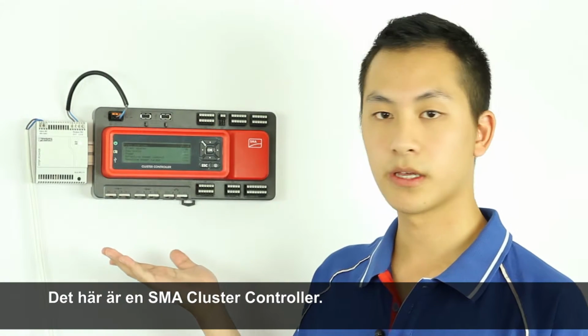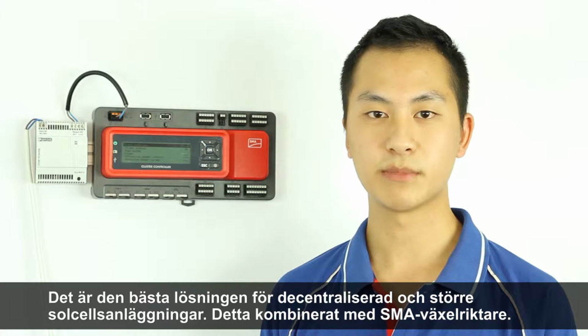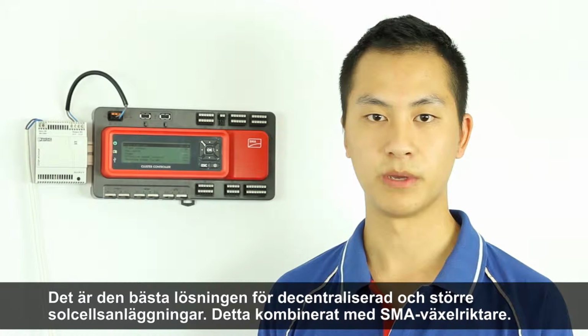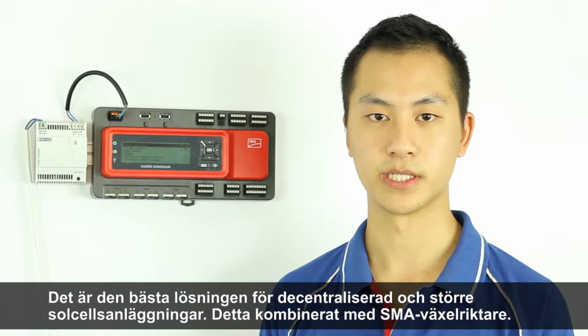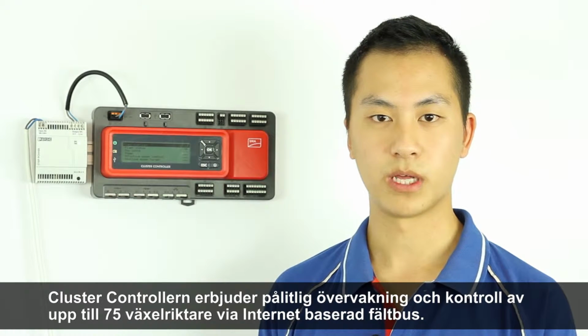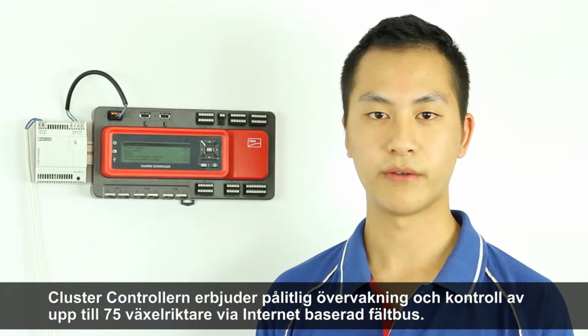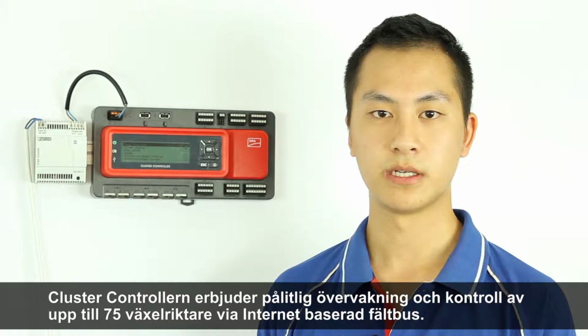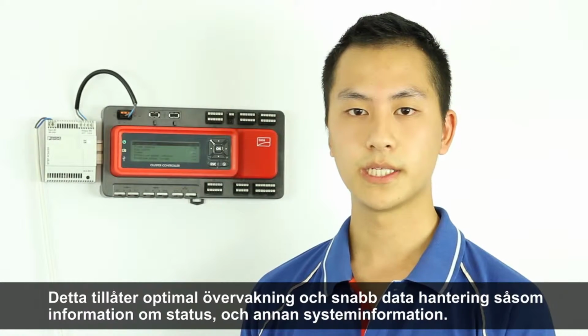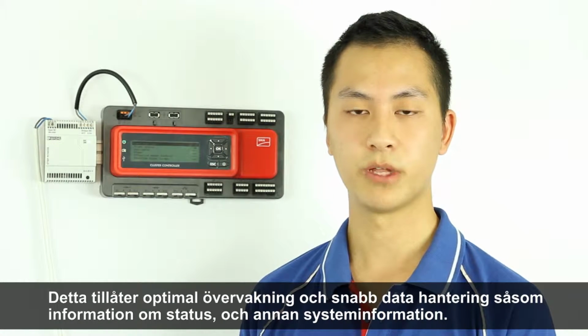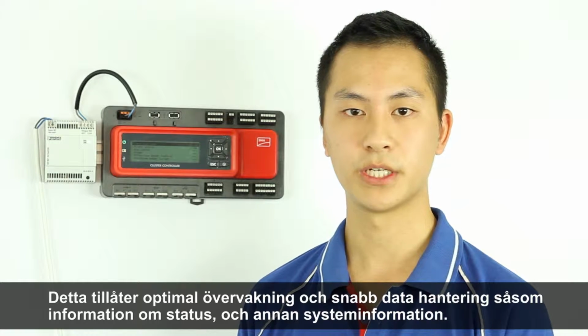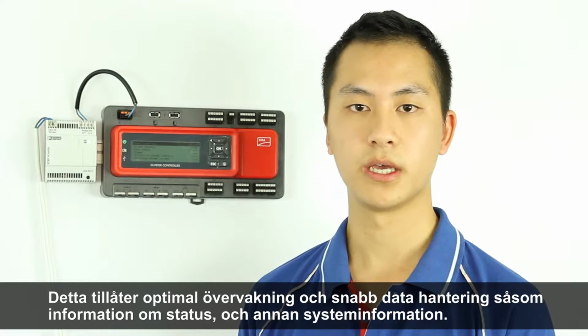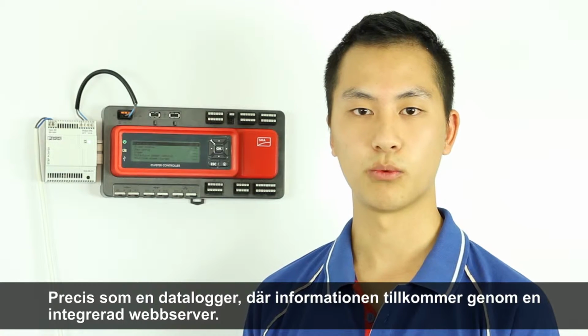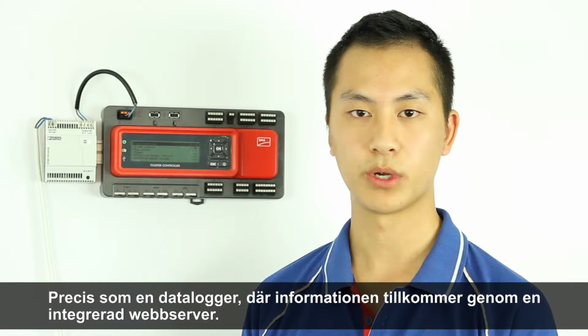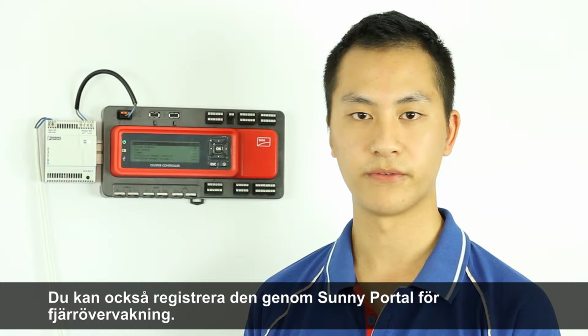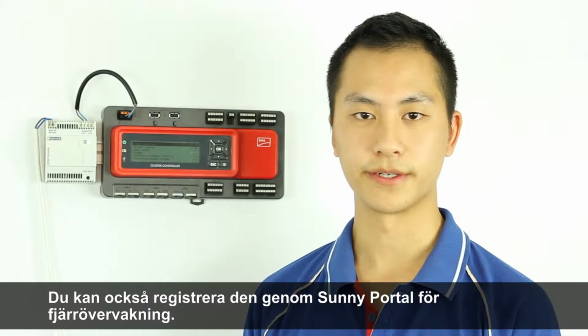Here is the SMA cluster controller, and this is the ideal system solution for decentralized large-scale PV plants when combined with SMA inverters. The cluster controller offers reliable monitoring and control of up to 75 inverters via the Ethernet-based SpeedWire field bus. This allows for optimum data transfer rates for plant monitoring and fast processing for measured values, status information, and system control commands. Just like the Webbox, the cluster controller comes with an integrated web server, and you can also register for Sunny Portal for remote monitoring.